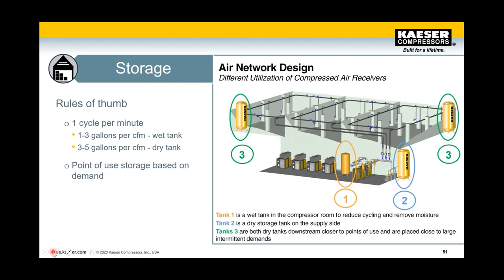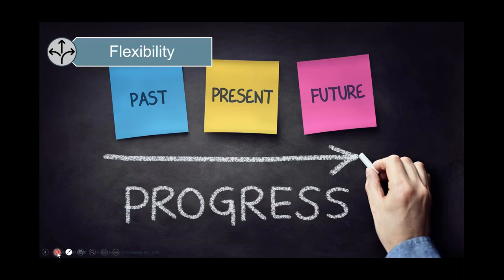We've already talked a lot about storage. Storage in the compressor room is critical to operation, as well as keeping compressors from overcycling, which can lead to increased service intervals or reduce the lifetime of major components — not to mention the potential effects on production when compressors shut down. Design with flexibility in mind. Best laid plans often go awry, so being flexible up front — for example, using multiple smaller compressors rather than one large one, or increasing your distribution header one size above what's called for — can really help when it comes to system dynamics in the future.